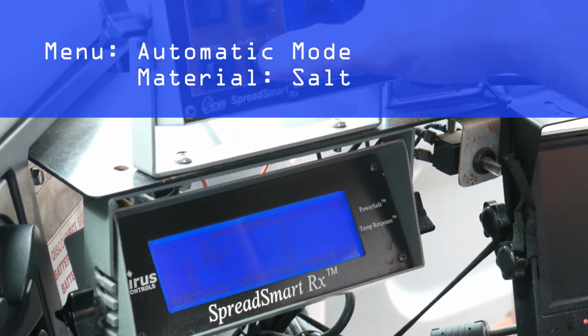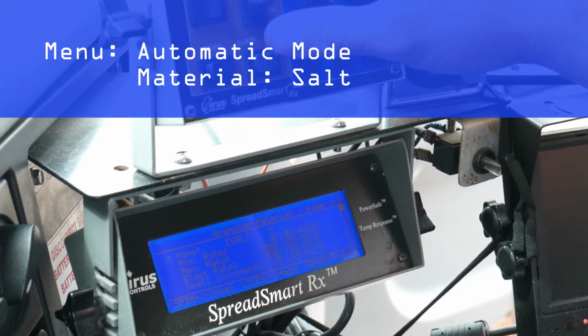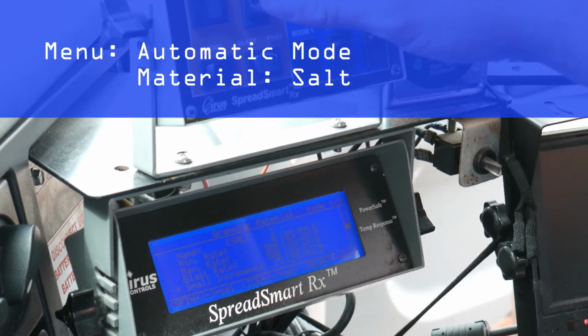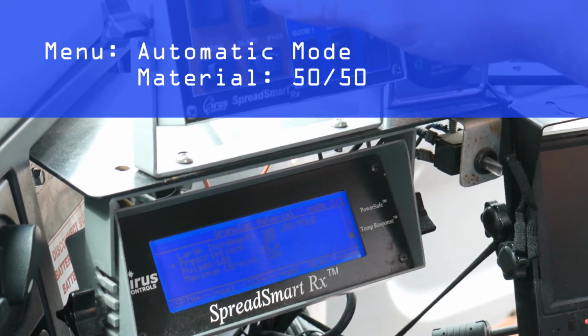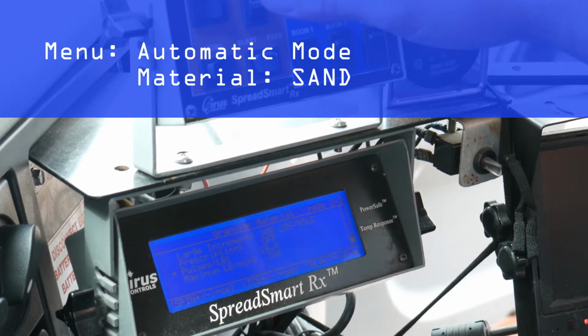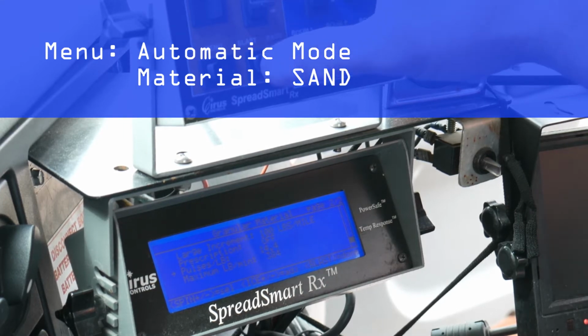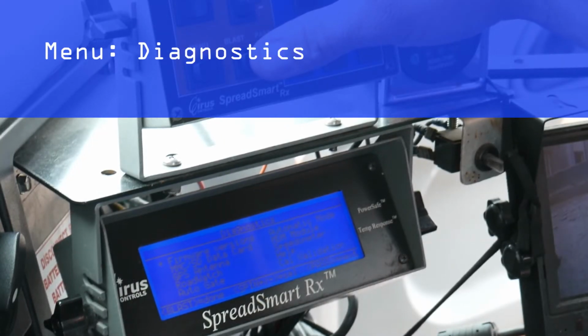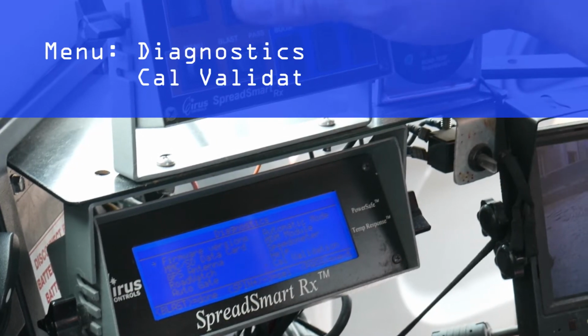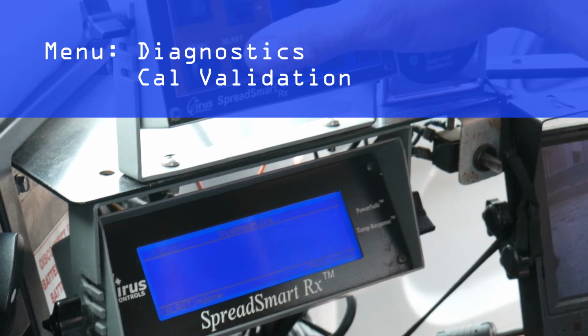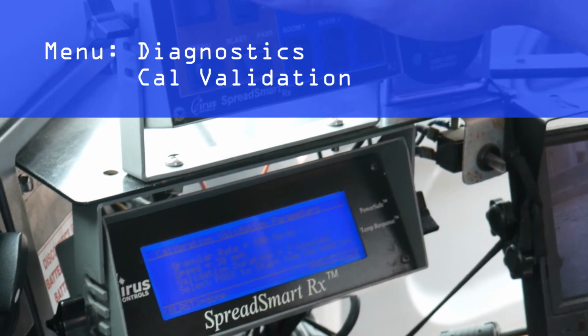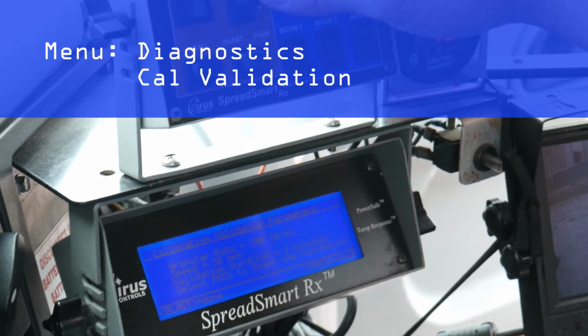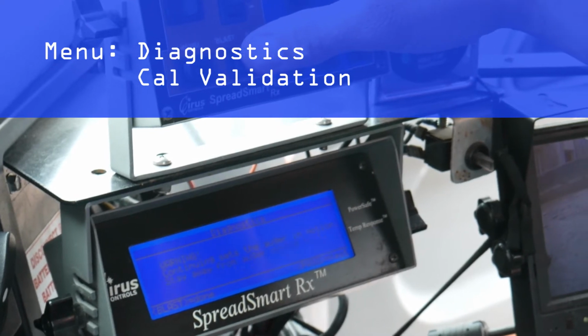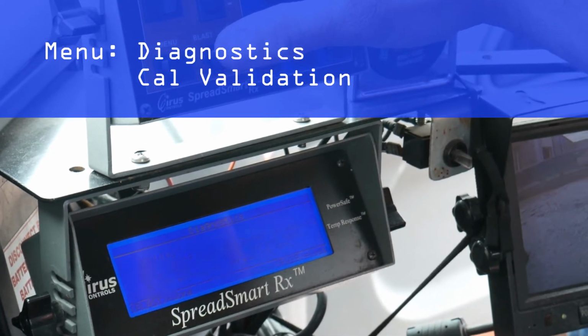It is very important that you repeat all the calibration steps for each material you use, including salt, 50-50 mix, and sand. Using the same calibration numbers for all materials will not work. Return to the main menu and select Diagnostics, followed by Calibration Validation, sometimes abbreviated as Cal Validation or CalVal. The screen will then display the test parameters.